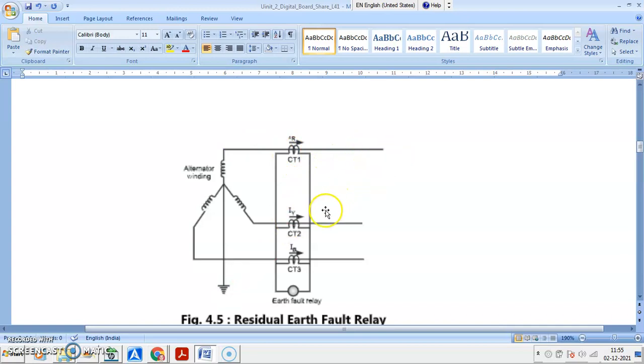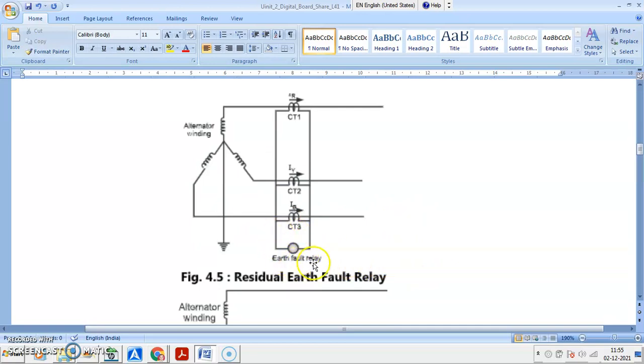This is current supplied by R phase, Y phase, B phase: IR, IY, IB. This is earth fault relay. Whenever you are having the star connected winding, CT secondaries are connected in star. So secondary 1, 2, 3 star, secondary 1 dash, 2 dash, 3 dash. So all three dash terminals are connected in star, and the earth fault relay is connected.